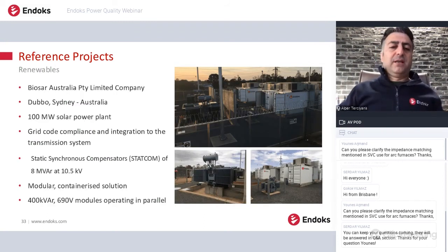And this reference project is coming from Australia. This is a STATCOM project, actually in Sydney, Dubbo. It was installed in order to meet the grid codes in Australia with a 100 megawatt solar power plant, because in order to operate the 100 megawatt solar power plant, there should be reactive power support and also voltage ride-through capability. And we provided this capability using a STATCOM. Actually, it is an 8 MVAr STATCOM connected to a 10.5 kV bus using coupling transformers. We have four containers. It's a containerized solution. In each container, we have 2 MVAr, and each 2 MVAr is composed of modules of 400 kVAr at 690 volts.